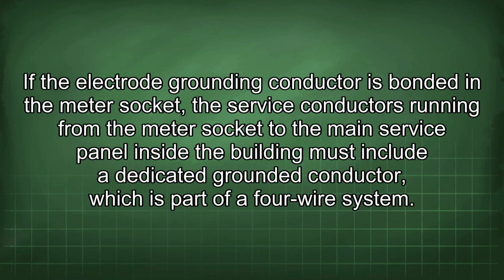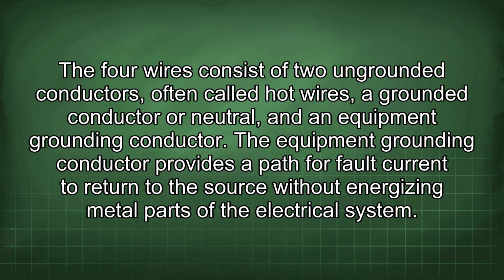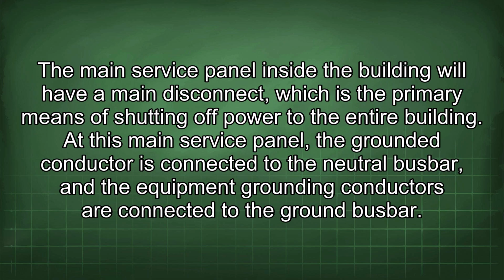If the electrode grounding conductor is bonded in the meter socket, the service conductors running from the meter socket to the main service panel inside the building must include a dedicated grounded conductor, which is part of a 4-wire system. The 4 wires consist of 2 ungrounded conductors, often called hot wires, a grounded conductor or neutral, and an equipment grounding conductor. The equipment grounding conductor provides a path for fault current to return to the source without energizing metal parts of the electrical system. The main service panel inside the building will have a main disconnect, which is the primary means of shutting off power to the entire building. At this main service panel, the grounded conductor is connected to the neutral busbar, and the equipment grounding conductors are connected to the ground busbar.